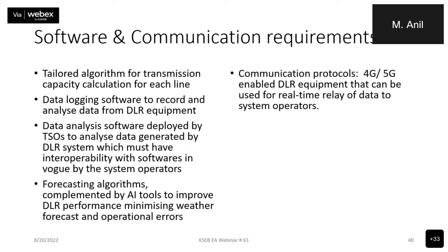Software and communication requirements. A tailored algorithm for transmission capacity calculation is needed for each line, because each line has typical characteristics: the line material will be different, the ambient temperature of the site will be different, etc. Data logging software is required to record and analyze data from the DLR equipment. Data analysis software deployed by transmission system operators to analyze data generated by the DLR system must have interoperability with the software used by the system operators. Forecasting algorithms complemented by AI tools to improve DLR performance, minimizing weather forecast and operational errors. And communication protocols: 4G, 5G enabled DLR equipment can be used for real-time relay of data to system operators.